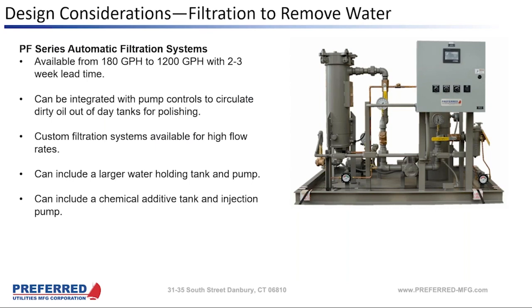A word of warning: those other additives can be seen as an end-all be-all for a diesel system. We've had experience in the past where many of those water mitigation additives that you buy a certain volume of and dump in a tank, the problem is they don't actually turn water to fuel, right? It's not alchemy or magic. What they do is they tend to disperse it. And that's one thing if you're about to burn the fuel in an engine or especially a boiler right away, and you don't want a slug of water going in. But if you have a system like most systems here in the Northeast where you have a large amount of fuel stored over a long period of time, dispersing the water can be the worst thing you can do, especially if you don't have anything like a polishing unit to then pull the water out, especially water that's suspended in the fuel, because you took a problem of fuel quality that really was at the bottom of the tank, right?